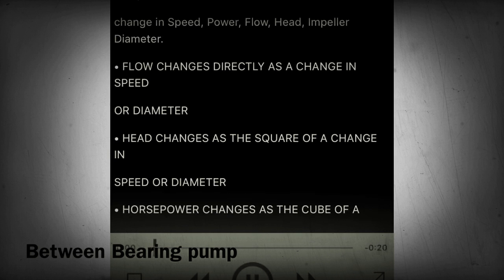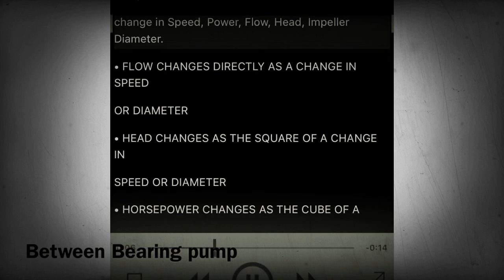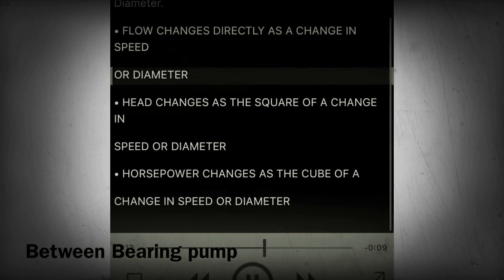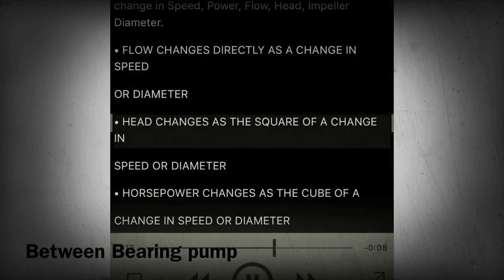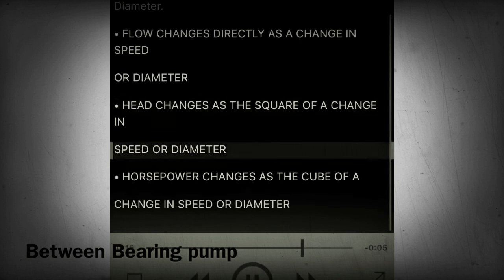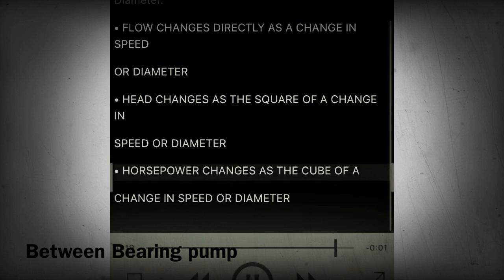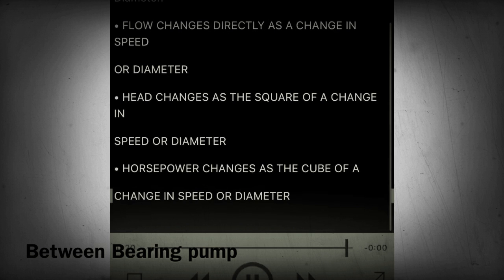Section 35 - Affinity laws. Affinity laws describe the performance of centrifugal pumps based on changes in speed, power, flow, head, and impeller diameter. Flow changes directly as a change in speed or diameter. Head changes as the square of a change in speed or diameter. Horsepower changes as the cube of a change in speed or diameter.